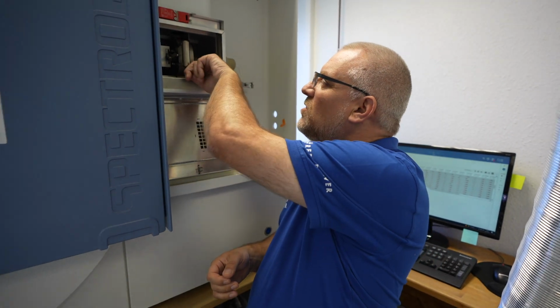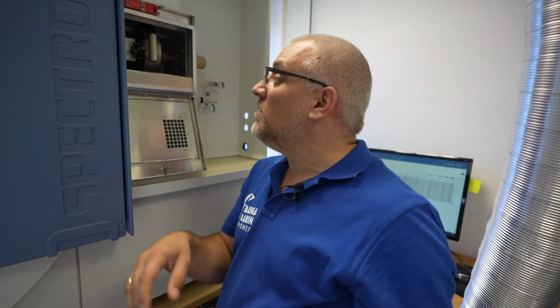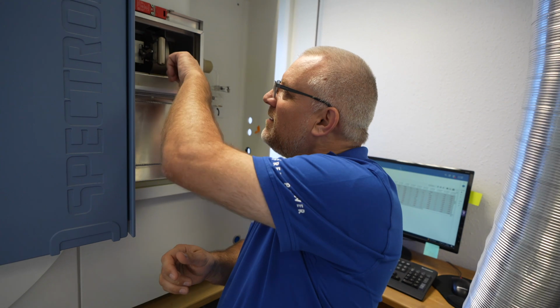The fact is that this machine has some big issues with seawater testing, because it collects all the dirt and the salt, and every time the flame hits the salt, it creates additional light information which has to be calculated out of the result. So if you're lucky and you test in the first 10 or 20 tests, then the machine is quite good. It's maybe 1% more exact than the other one. But after these 10 or 20, when it is full of salt, the accuracy and the precision go down massively. So you have to recalculate.